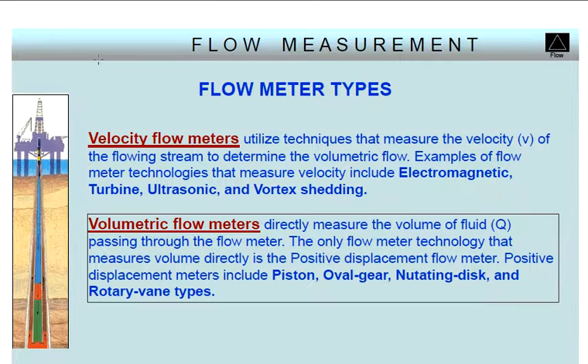Volumetric type flow meters directly measure the volume of fluid passing through the flow meter. The only flow meter technology that measures volume directly is the positive displacement flow meter. Positive displacement meters include piston, oval gear, nutating disc, and rotary vane types.